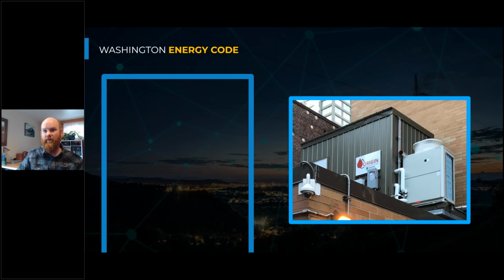But just walking through this picture, we of course have a CO2 heat pump water heater right here. So really highly efficient heat pump water heater. And we have some pipes, a cool water and a hot water pipe going to this building, this mechanical penthouse where there's water storage tanks. And so this is feeding into the existing water heating system in the building. And if this system is working well, and it has been, this is providing all the domestic hot water heating to the building, and the existing system is there for backup in case this goes down for some reason. So there have been multiple demonstrations that Ecotope has done, that other engineering firms have done throughout the region, that have proven that these heat pump water heating systems can be successfully implemented in both retrofits and new construction.